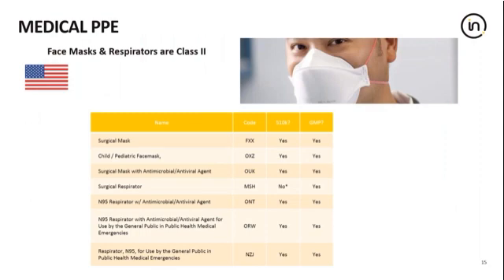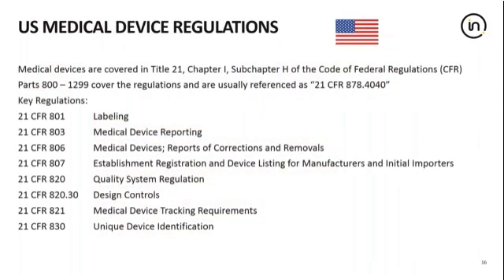And from the classes, a face mask and respirators are class 2 medical devices. And this means that they would usually require pre-market approval. A surgical N95 respirator or N95 filtering face piece respirator is not exempt from this process if it is intended to prevent specific diseases or infections. And medical devices themselves are covered under the regulation 21 CFR 800 through to 1299. And the key parts of the regulation which are required are covered in this slide here.